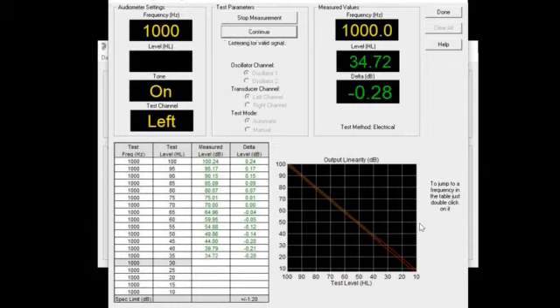Another thing, take a look. See if we're going down to 10 dB. I can go to minus 10 dB if you want to. Try to do that with a sound level meter. Most of the background noise levels and the linearity of the attenuator checks done on people with just a sound level meter, they usually will stop at about 20 dB. At least that's what I've seen coming back in from the field. Maybe not so much in manufacturing, because they control the environment. But if you're out in industry or in an environment that's noisy, try testing linearity down to 10 or to 0. See how successful you become.